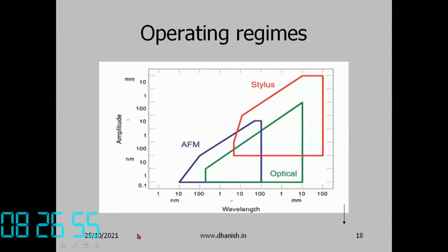So the different instruments have different operating regimes, the range of operation. The most sensitive is of course the atomic force microscope. It can start from a wavelength of 10 nanometers as the resolution. So very fine resolution is possible, up to say 100 nanometers. So this is nanometer, micrometer, millimeter. Up to 100 nanometers, atomic force is possible, and amplitude, the height, up to say 1 micrometer is possible. So for lower amplitude and lower wavelength, atomic force is sensitive.